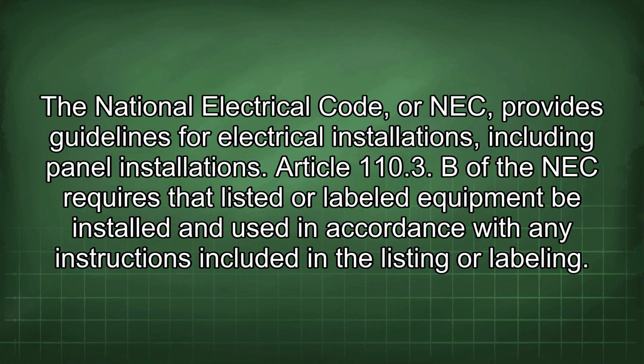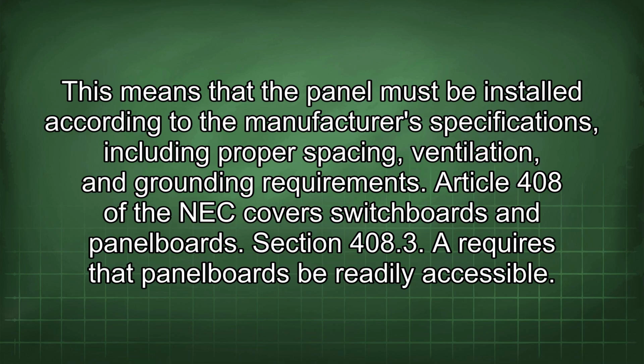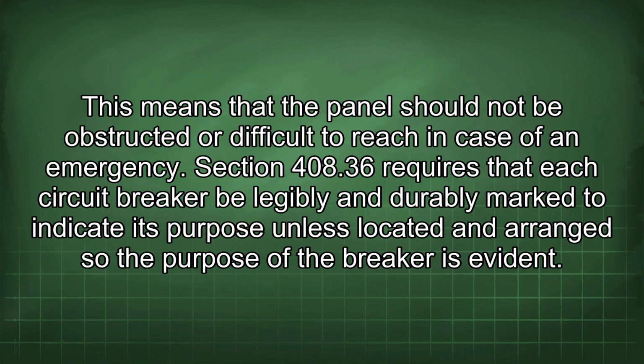The National Electrical Code, or NEC, provides guidelines for electrical installations, including panel installations. Article 110.3(B) of the NEC requires that listed or labeled equipment be installed and used in accordance with any instructions included in the listing or labeling. This means that the panel must be installed according to the manufacturer's specifications, including proper spacing, ventilation, and grounding requirements. Article 408 of the NEC covers switchboards and panelboards. Section 408.3 requires that panelboards be readily accessible. This means that the panel should not be obstructed or difficult to reach in case of an emergency.